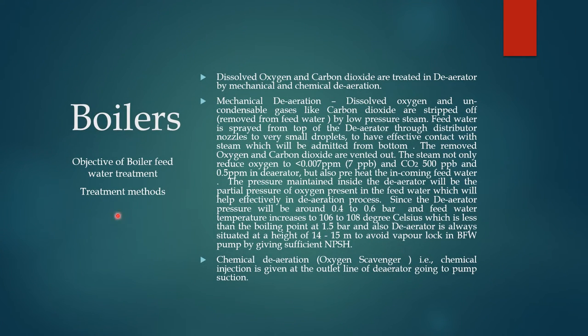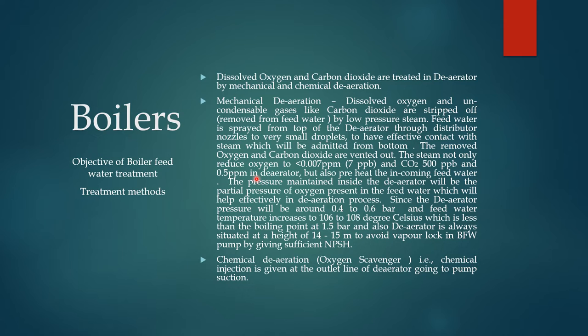The objective of boiler feed water treatment and the treatment methods: dissolved oxygen and carbon dioxide are treated in a deaerator by mechanical and chemical deaeration. Mechanical deaeration removes dissolved oxygen and non-condensable gases like carbon dioxide, which are stripped from feed water by low-pressure steam. Feed water is sprayed from the top of the deaerator through distributor nozzles into very small droplets for effective contact with steam admitted from the bottom. The removed oxygen and carbon dioxide are vented out. Steam reduces oxygen to less than 0.007 ppm and carbon dioxide to 0.5 ppm (500 ppb) in the deaerator.